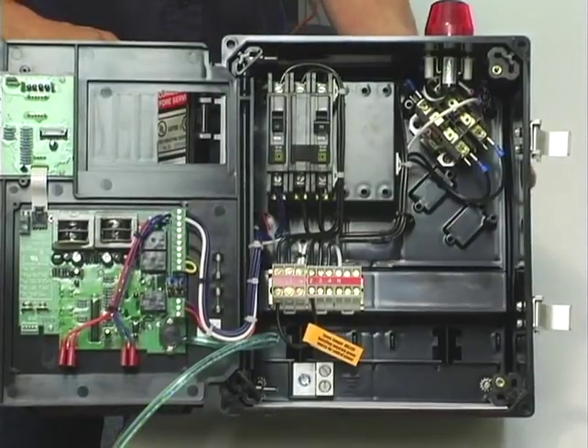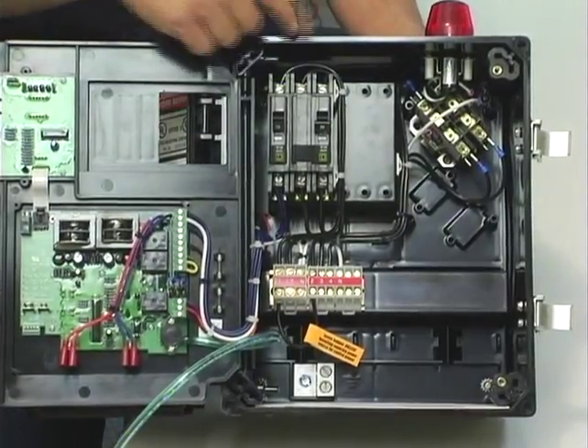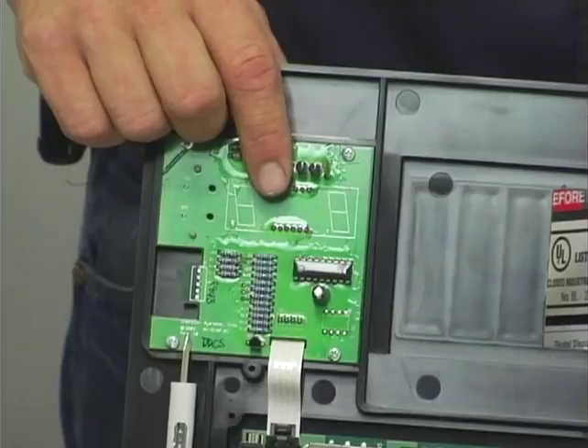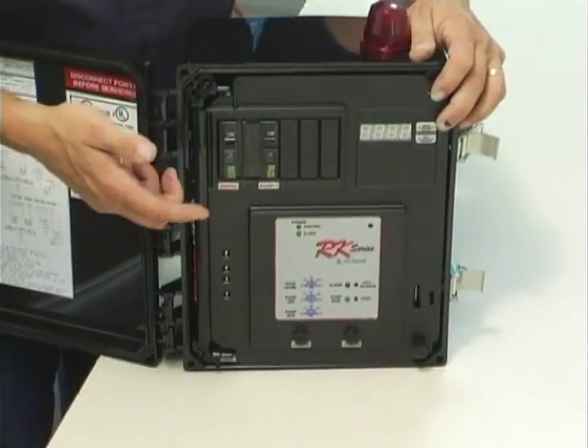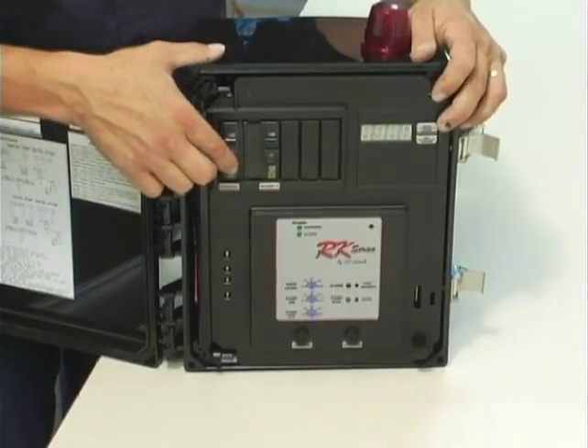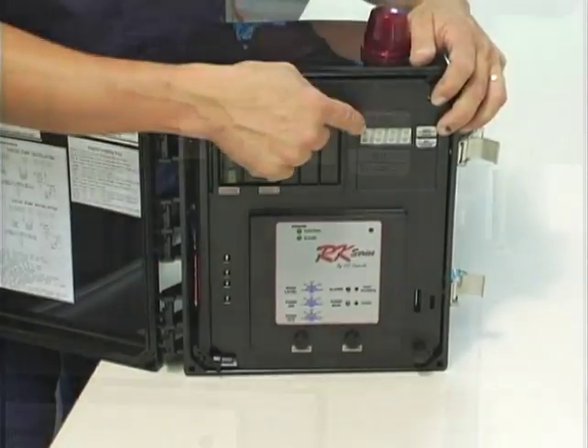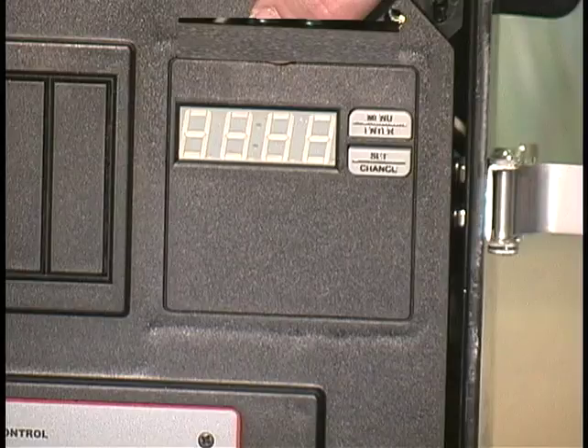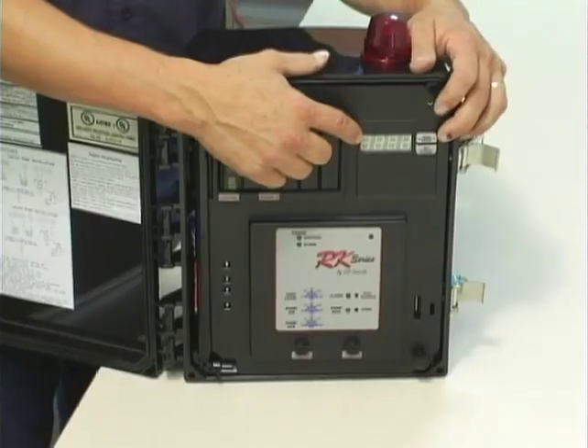There are no elapsed time meters and cycle counters in this control panel because they're all on the digital display that's on the door. The main problems that you'll see with this control panel, or what you'll want to check when you come out, is the digital display in the corner. It's going to give you your liquid level reading in the tank.